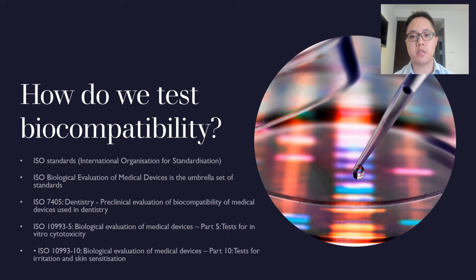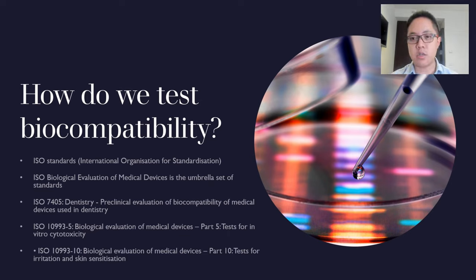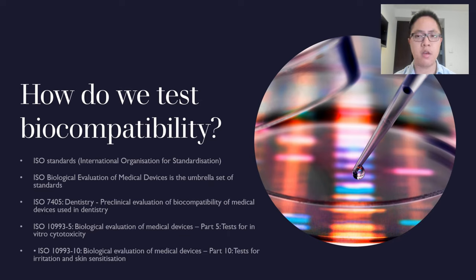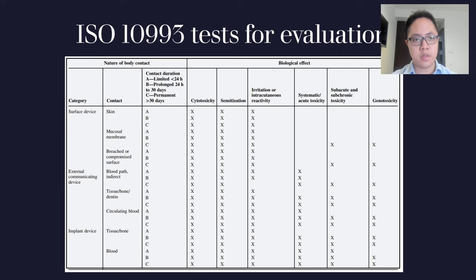How do we test biocompatibility? We have global standards called ISO standards, several of which are particularly relevant to dentistry: ISO 7405, specific to dentistry; ISO 10993 for measuring in vitro cytotoxicity; and ISO 10993 for irritation and skin sensitization. There are many other criteria out there too. Here are some ISO 10993 tests for evaluation — there's a whole range of criteria that can be assessed.